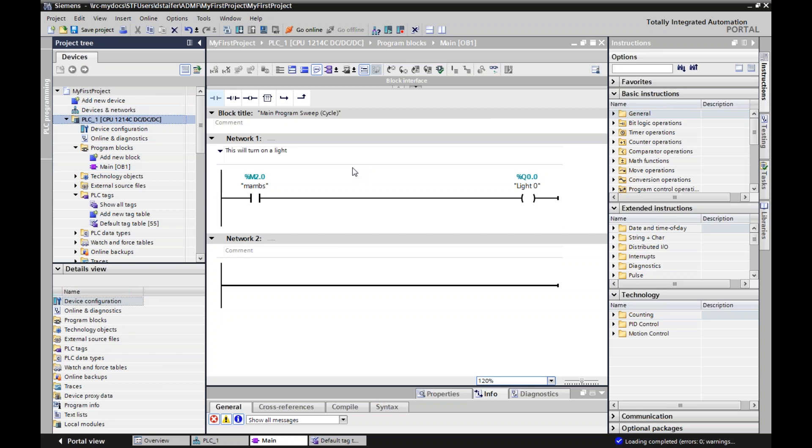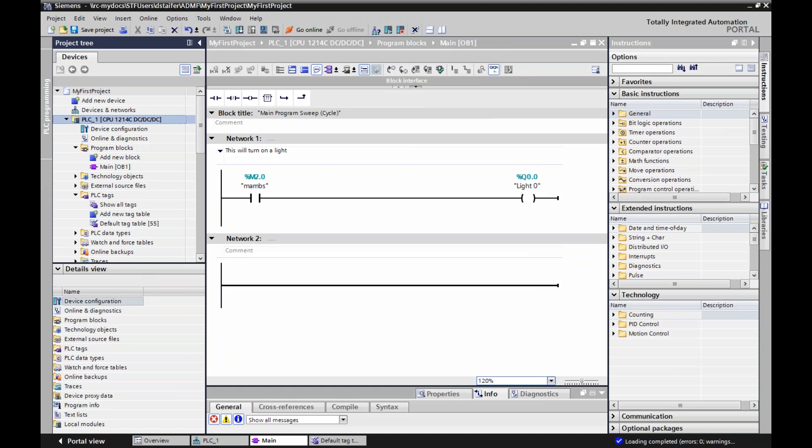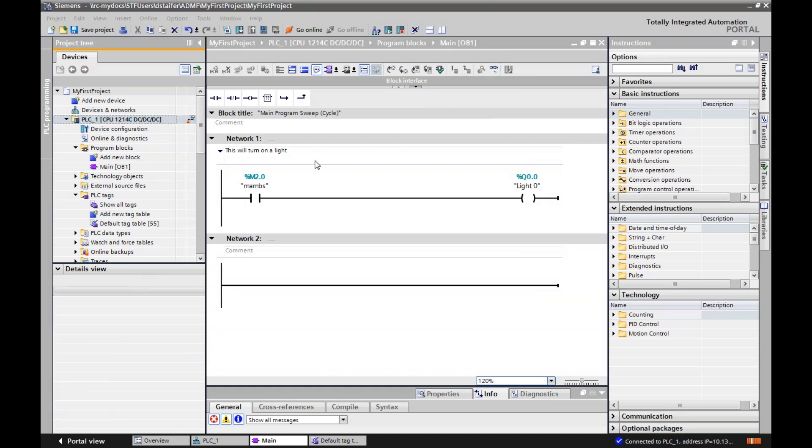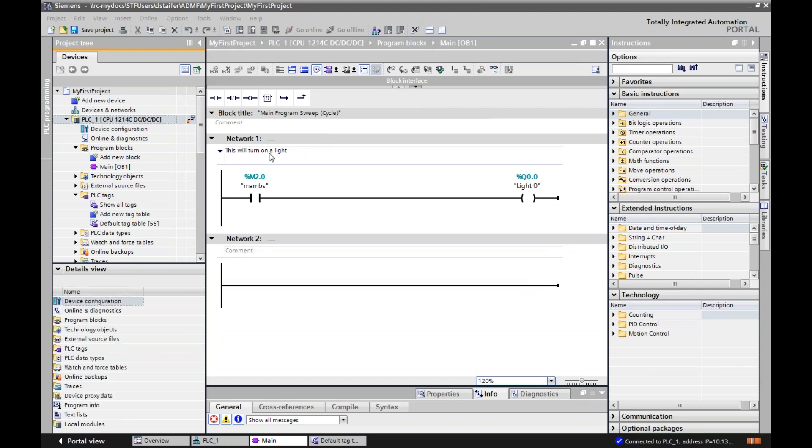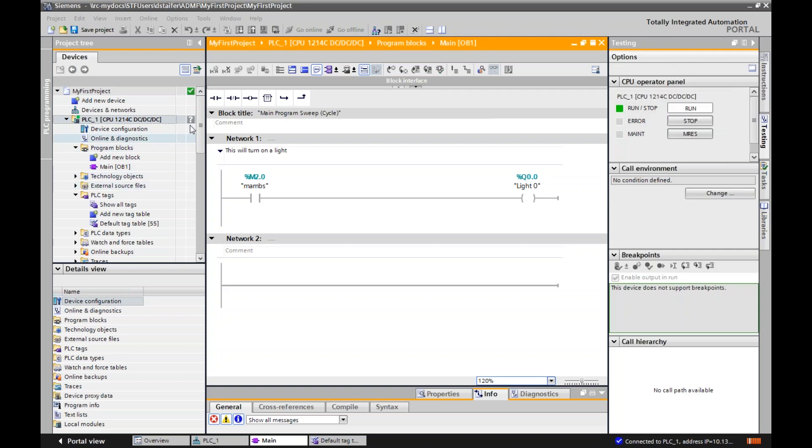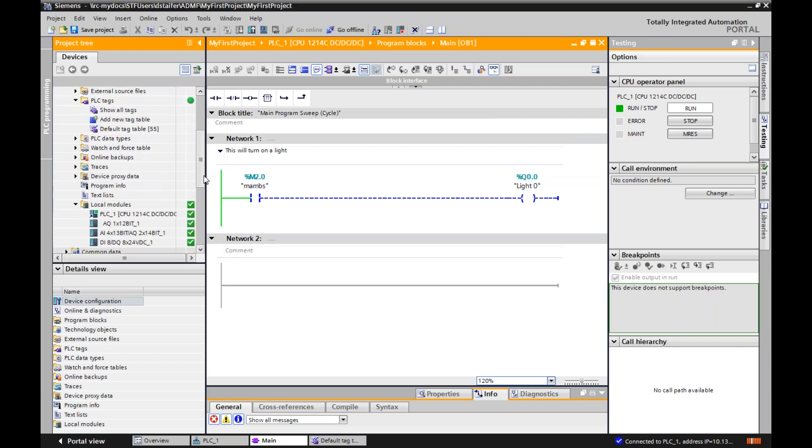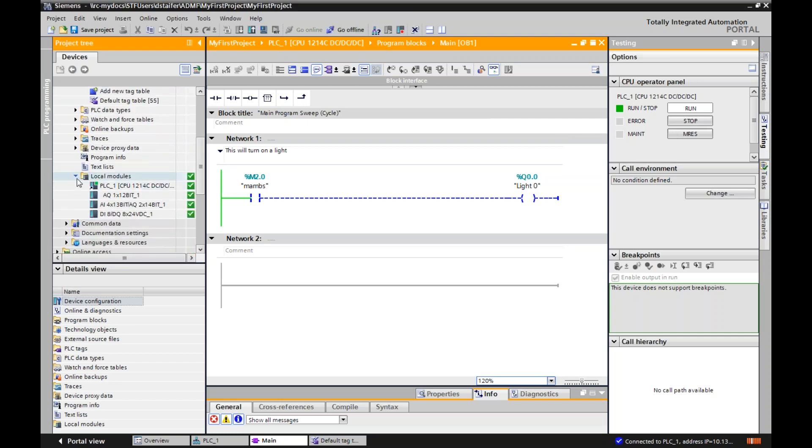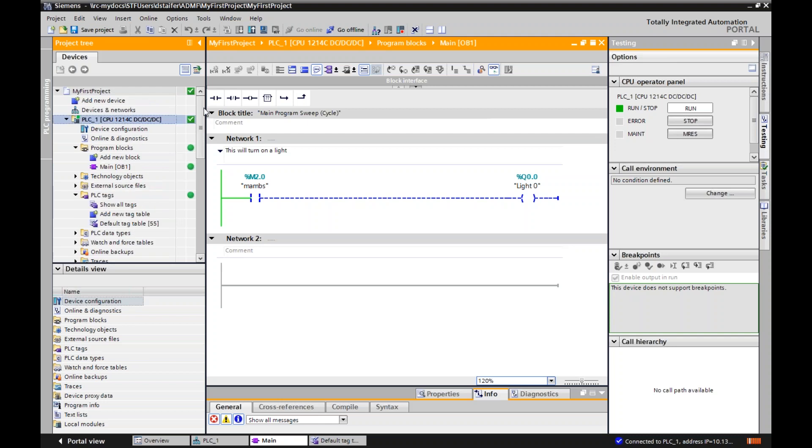So right now I'm not online with it directly. So if I want to monitor online changes, I can't. What I need to do is go two things. One, I can go online or what I like to say is put the sunglasses on. This is monitoring. And if I do this, this will allow me to go online to monitor. So you can see that right here. And if you see orange, it means you're online. A couple other things to keep in mind is check over here the color of the boxes. If everything is green, that means it's good. If it's orange, you may have made a change online. You need to redownload. I'll show you that in a second. Or if it's red, you're having an error. Sometimes your hardware will give an error if it's not compiled right. So you may need to recompile and download. So keep that in mind.